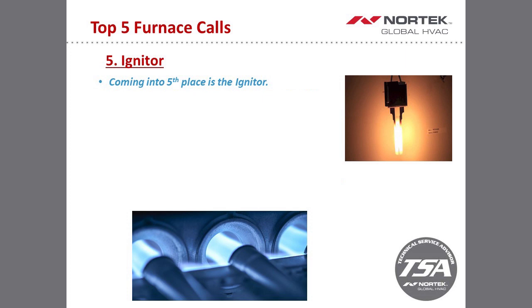So coming in at 5th place is the igniter from a troubleshooting standpoint. This is going to be very straightforward as far as troubleshooting in general. The igniter is going to be a 115 volt part that comes from your control board. And again, this is where knowing the startup sequence will greatly help you. If you are going through a startup sequence and you don't see the igniter kicking on, from a troubleshooting standpoint, make sure you're actually getting line voltage to the igniter, because if you're not, that may be a board issue. If you are getting line voltage to the igniter, then we may have an igniter problem.